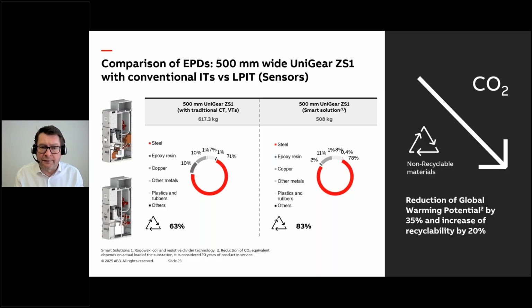There are two main contributors to this difference. The first is the steel, because we have a more narrow panel and a different design for the assembly of the traditional voltage transformers versus the sensors. The second main contributor is the weight difference between the different measuring technologies.